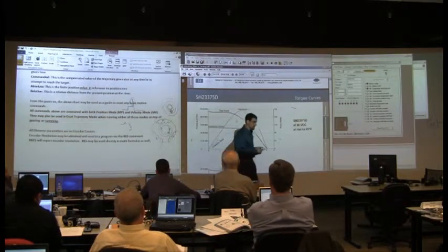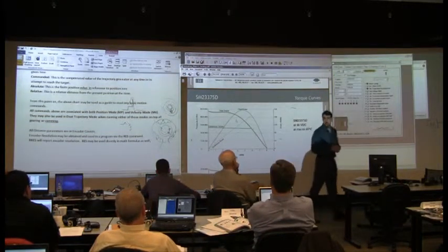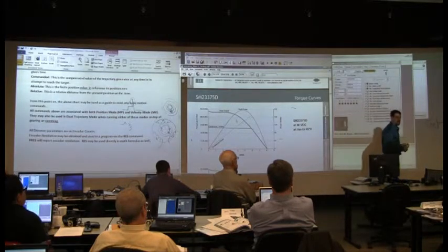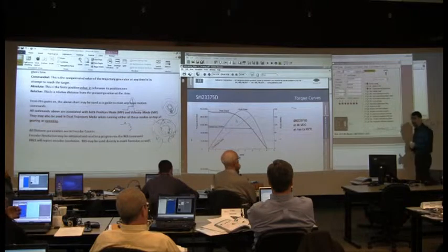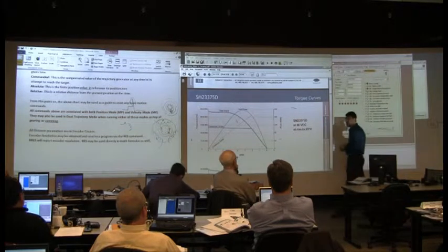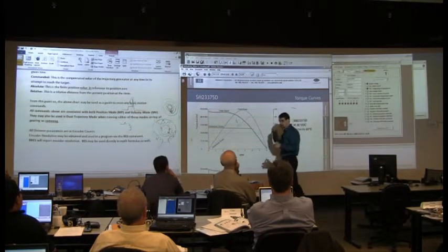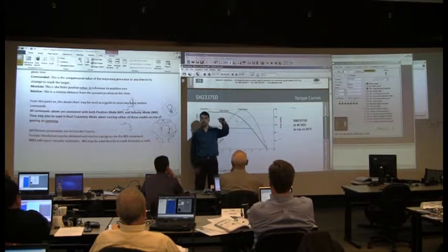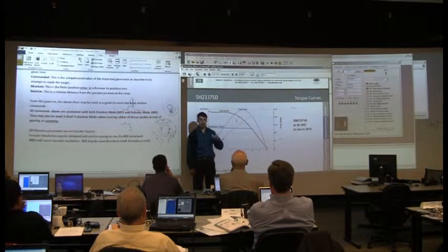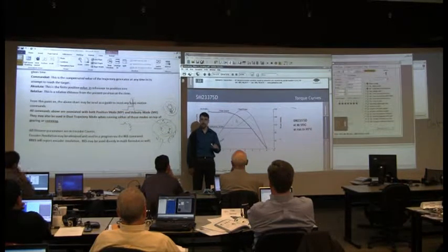Well, the same thing happens inside the windings. The other day, it was Dan on the phone, and he says this customer's getting back EMF, and he's getting overvoltage only when he goes down, not when he goes up. He's got a vertical application. Water goes up, water goes down. He kept getting an overvoltage trip going down. Why?